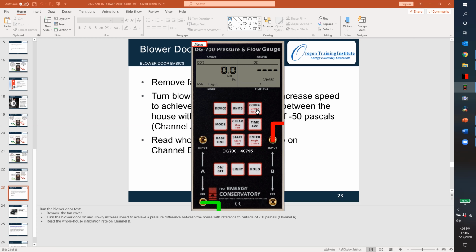The manometer should handle it most of the time, but if you can't get very much pressure, there is a manual calculation. Usually it's printed right on the fan control, but definitely in the manometer instruction manual. So at like 25, if that was the highest pressure you could get, your first instinct is, okay, I just double it.